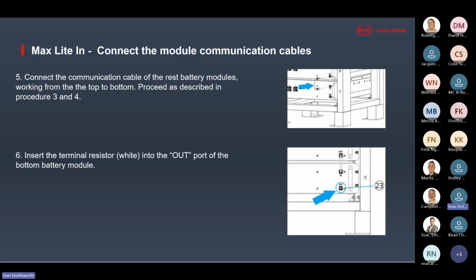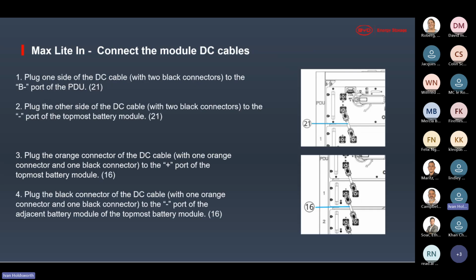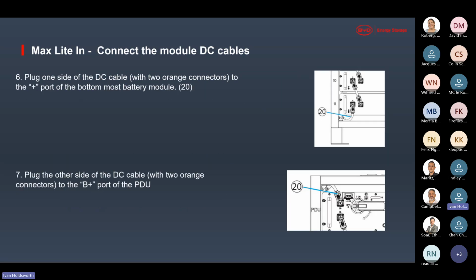If you have any issues on site, please remove the termination resistor in the PDU and the termination resistor on the last module and put them in your hand or on a surface, and just check which is which. The termination resistor on the last module is white. The termination resistor on the PDU is light gray. Sometimes, due to lighting, it looks like one is the other. There are going to be labels in future on those termination resistors to make sure it's easily distinguishable. And you can see the daisy chaining of your power from the PDU to your modules. There's the last module, and there's the cable that links the PDU to the last module.